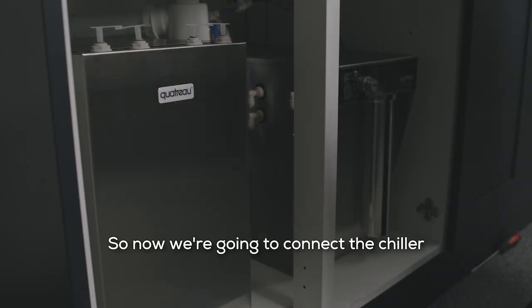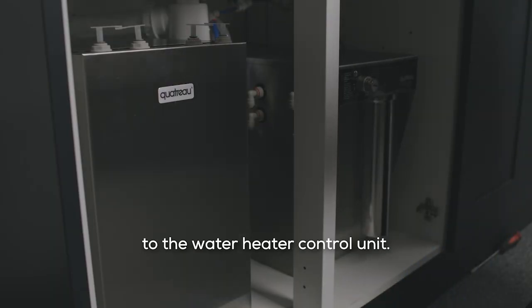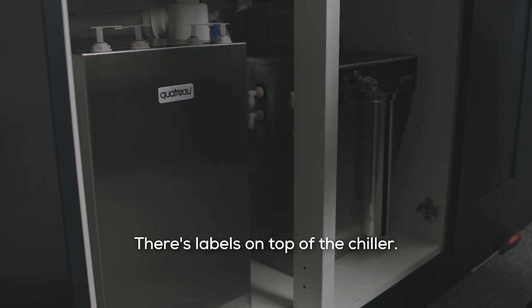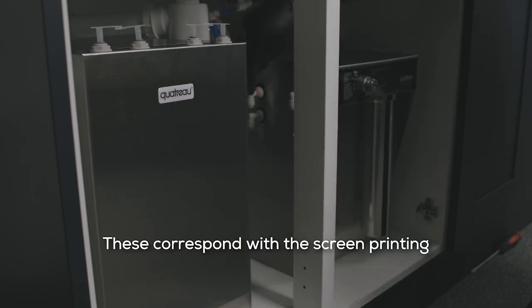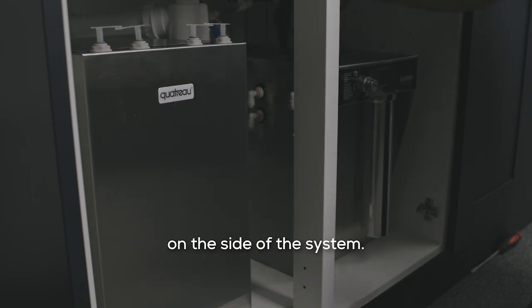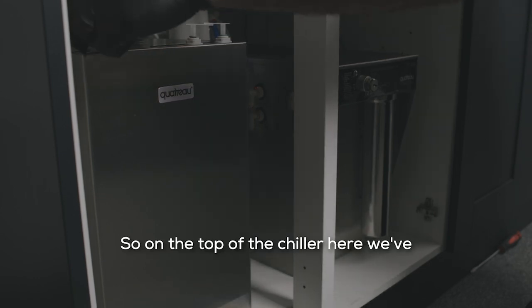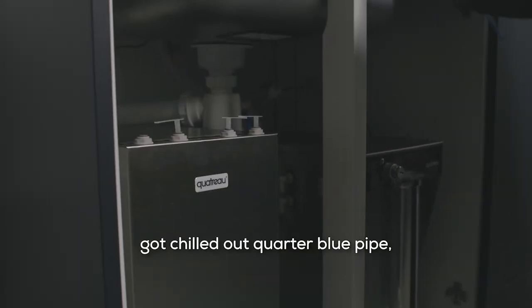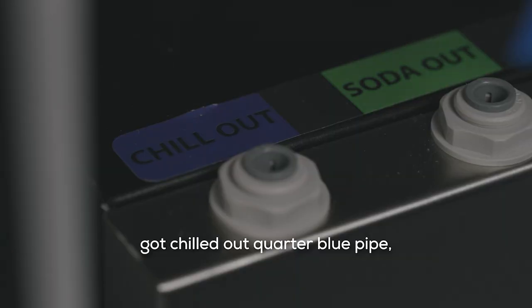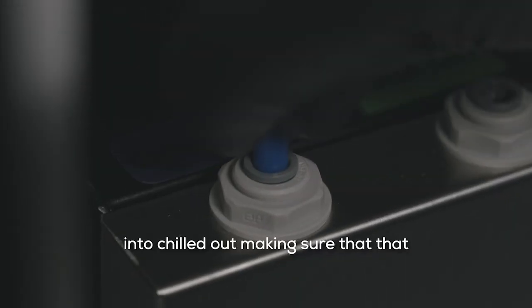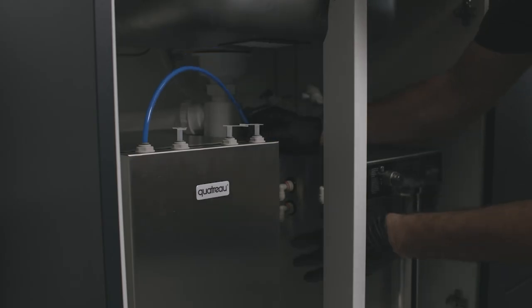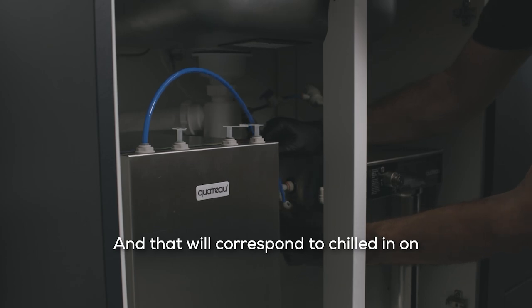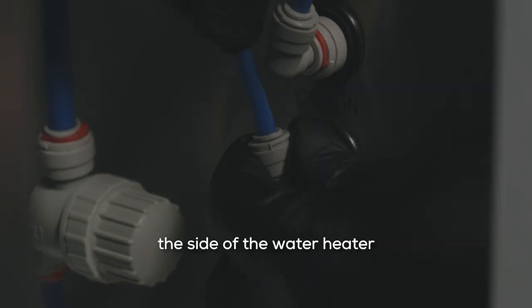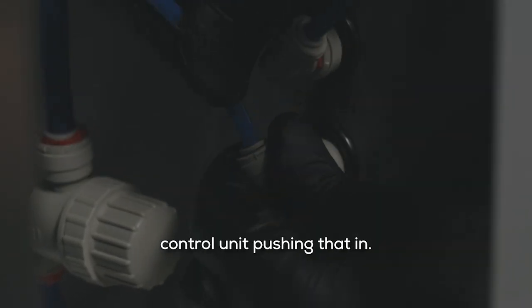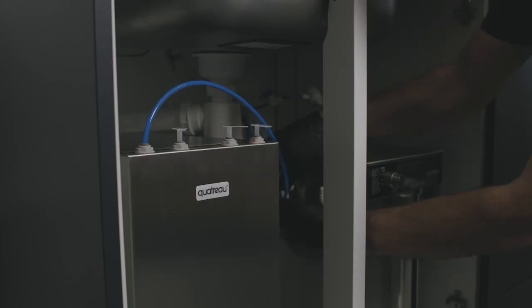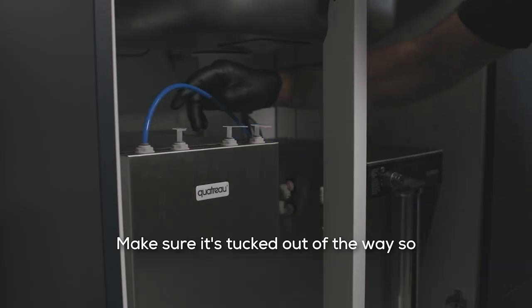So now we're going to connect the chiller to the water heater control unit. There's labels on top of the chiller. These correspond with the screen printing on the side of the system. So on the top of the chiller here, we've got chilled out, quarter blue pipe, into your chilled out, making sure that collar is locked in, and that will correspond to chilled in on the side of the water heater control unit. Pushing that in, make sure it's tucked out of the way so you're not going to bash it.